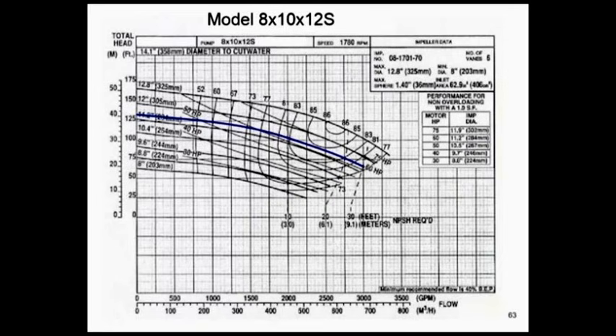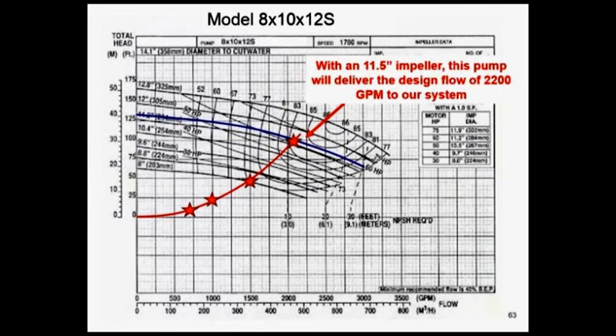Now, I've got this pump picked. Where's the pump going to run? The pump's going to run where we put that system curve across it. In this case, the system curve, we just plotted it. And we just see where the red star crosses the impeller curve is where the first law of thermo comes in. Pump energy in from the pump has to be energy out from the system curve. So there's only one place that pump can run. That's where that system curve crosses the pump curve. It can't run any place else, period. I don't care what's going on, it cannot run any other place.